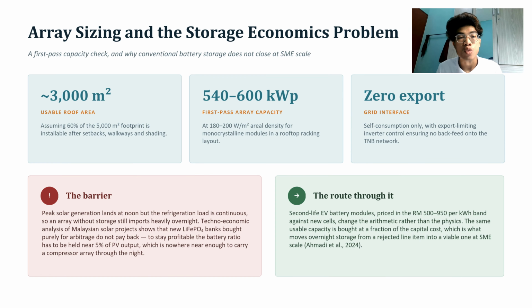So, how big is our solar system? We have about 3,000 square meters of usable roof space, which gives us roughly 540 to 600 kilowatts of solar panels. And importantly, this system does not send power back to the TNB, but only powers our own facilities. But here is a real problem. Solar panels produce the most power around midday, but the cold room needs power all day and all night. So without a battery, we would still need a lot of grid power at night.